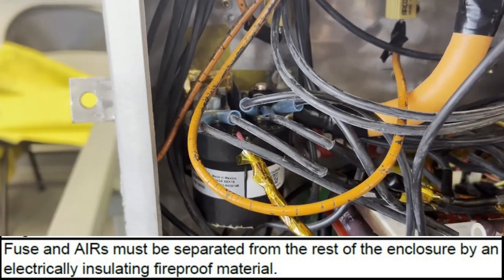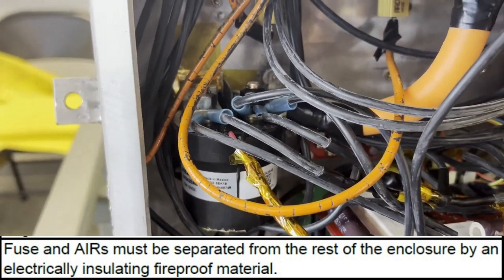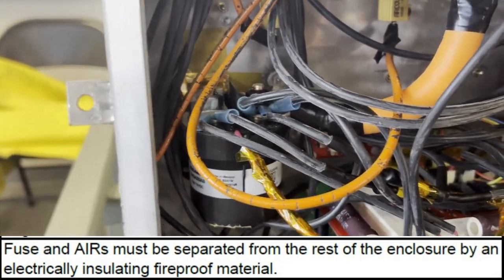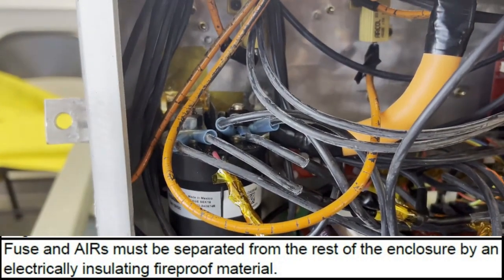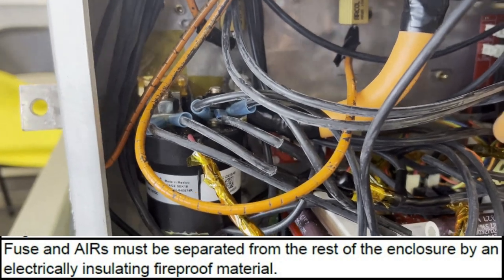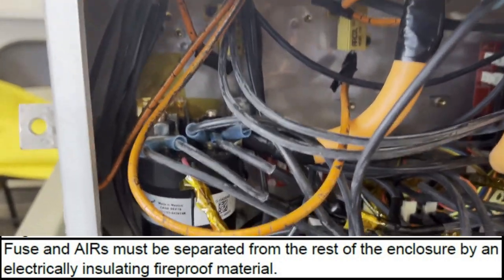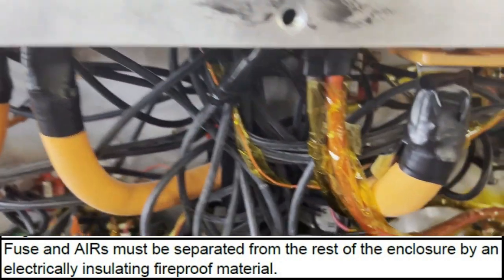Both AIRs, as well as the fuse, are protected from the aluminum wall of the accumulator enclosure by a piece of polycarbonate, which I'm tapping on here, that separates the entire back of the high voltage enclosure from the aluminum wall of the container. Just showing that the polycarbonate spans the entire back wall of the enclosure, tapping on it again here.